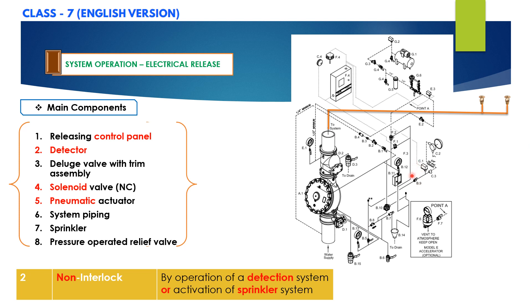In short, in a non-interlock pre-action system, the pre-action valve will be activated upon either operation of the solenoid valve or pneumatic actuator. Once either operates, water will flow into the system piping. To operate the valve manually, an emergency release can be pulled so that pressure is released from the priming chamber. The deluge valve opens but water is contained in the sprinkler piping until a sprinkler head opens. The water motor alarm and alarms connected to the fire alarm pressure switch will activate.